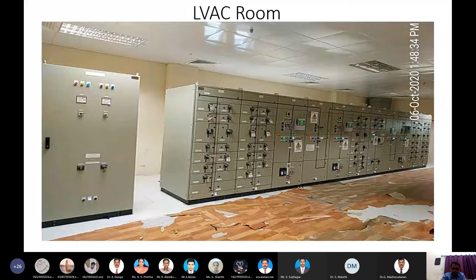What happens if the lockout tagout is not there and a person has switched off the plant and is working there? The other person may not know who is working, and if he accidentally switches the supply back on, we don't know what might happen to the person. He may be electrocuted, shocked, or burned. So this lockout tagout is mandatory for the LVAC room, as per the requirement in line with standards, and there is no compromise about that.